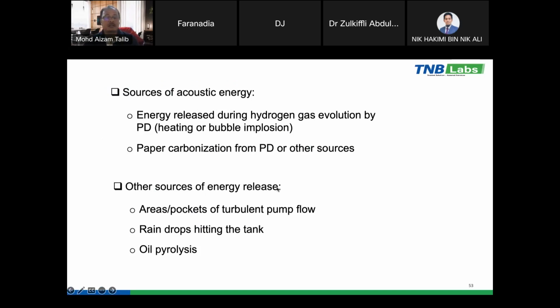Okay, sometimes the challenge is that other sources of energy, such as raindrops hitting the tank, will also be picked up by the acoustic sensor, and the overheating of the oil will also be picked up by the sensor. Sometimes when oil circulates in the transformer, it will generate a sound, and this will also be picked up by the sensor. So normally, to understand at what level the activity is active, we do the measurement for 24 hours, so we have a complete operating cycle of the power transformer.